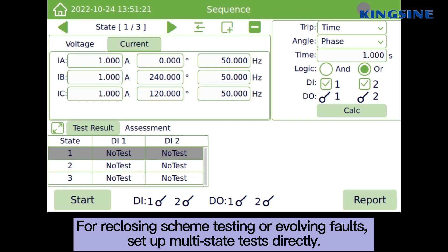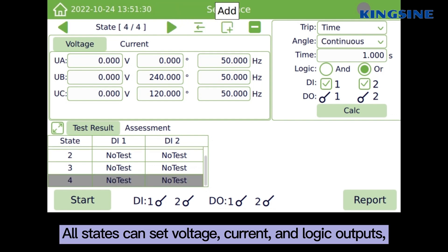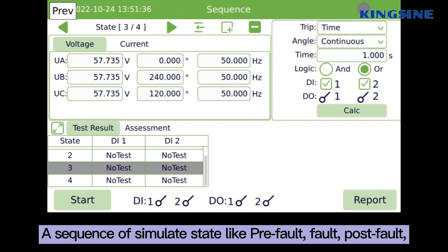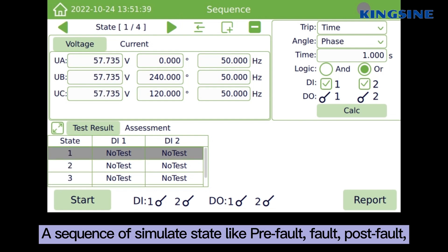For re-closing scheme testing or evolving faults, set up multi-state tests directly. All states can set voltage, current, and logic outputs. A sequence of simulated state like pre-fault, fault, post-fault.